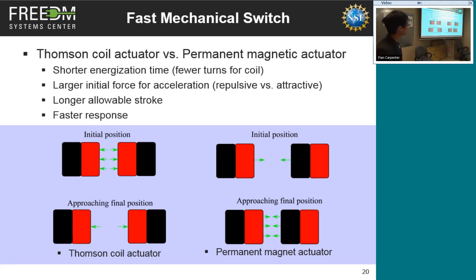Thomson coil actuator is based on repulsion force. We all played with magnets, so we know sometimes they attract each other, sometimes they repel, depending on the poles and position. Thomson coil is based on repulsive force, while the permanent magnetic actuator is based on attraction force. With two magnets, when do you feel the force is greatest? When they are closest. So you want to put them close to get a larger force. However, if you want them to attract each other, you have to put them far apart so they can move and transform that movement to the actuator and circuit breaker.